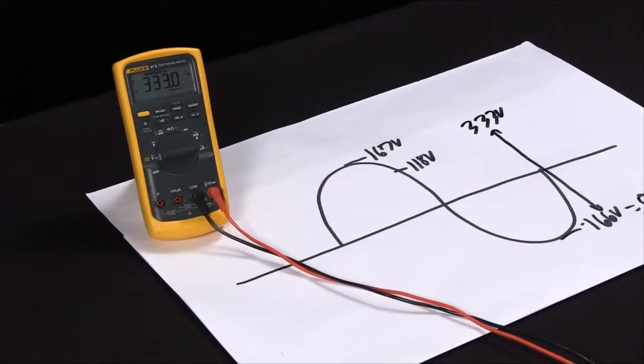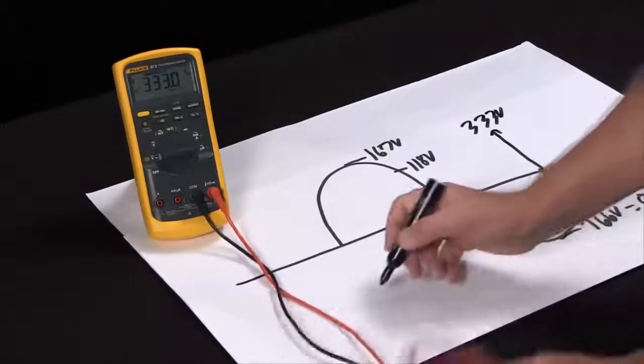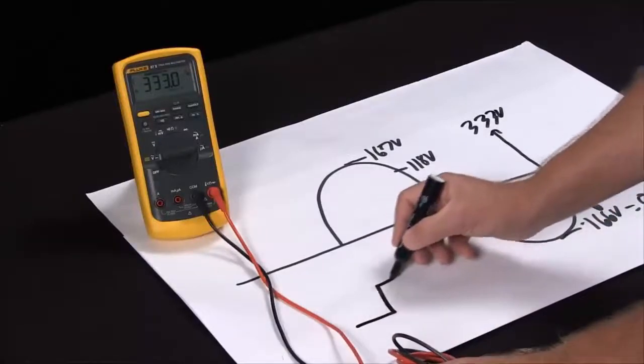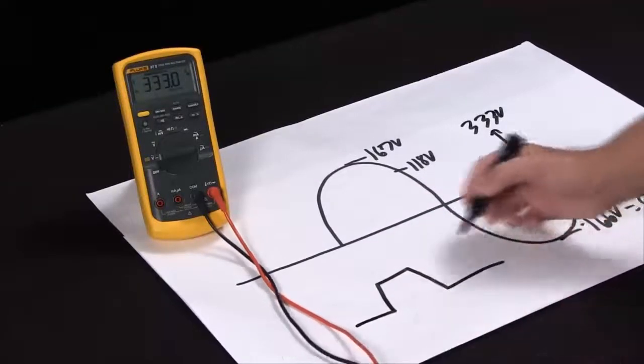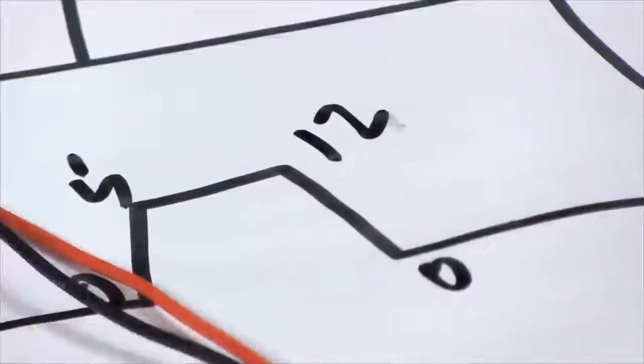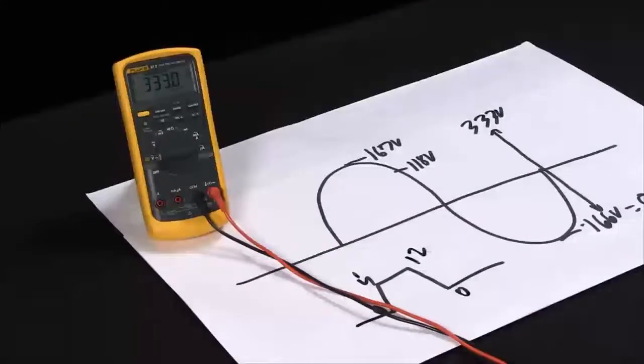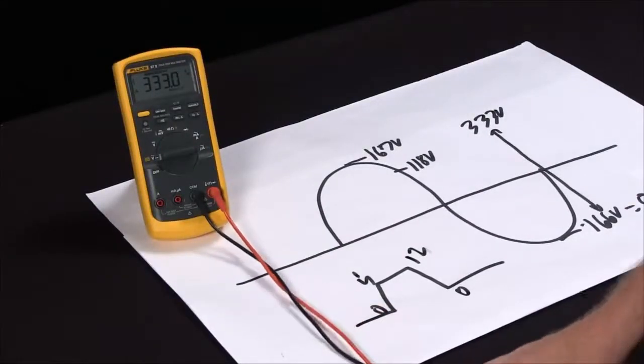Where for a sine wave this might not be so handy, when you're working on a square wave coming off an encoder what you really want to see is this zero to five volts, is it zero to 12 volts. So by having that relative mode and the peak min max you'll be able to check your square waves a whole lot better.